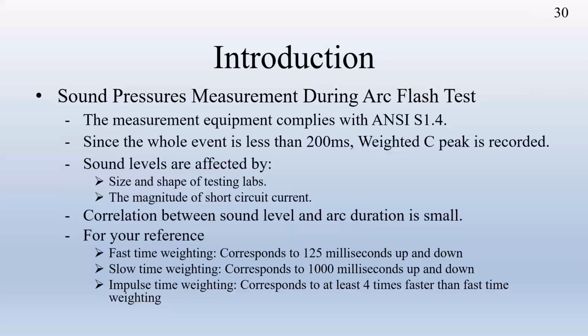So C weighted peak is recorded. When you do the experiment, the sound level is affected by the size and shape of the test lab and the magnitude of the short circuit current. The correlation between the sound level and the arc duration is very small, because the loud boom normally happens at the beginning, so the arc duration doesn't really change that much. We also look at fast time weighting, slow time weighting, and impulse time weighting, based on the specification.